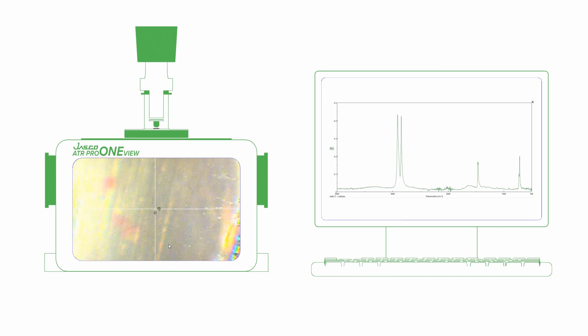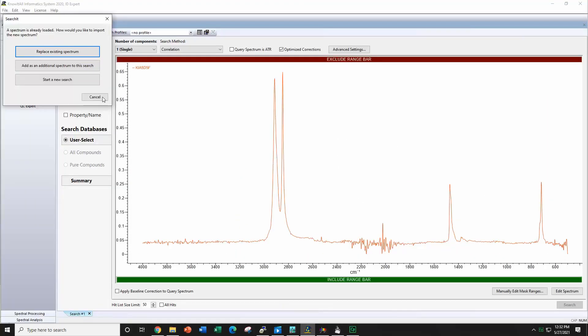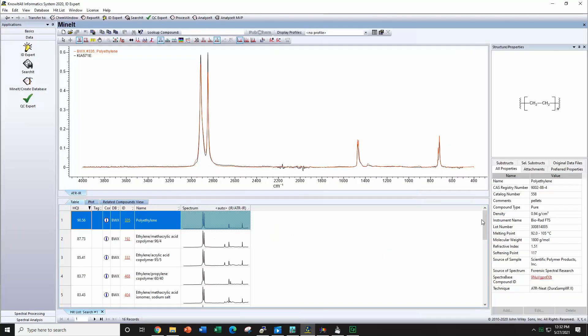In this case we are using an ATR Diamond Crystal. This sample is quite large, but it can be measured using the ATR accessory. We notice how the sample is in contact with the crystal. It is searched in the FTIR database and confirmed that this sample is polyethylene.